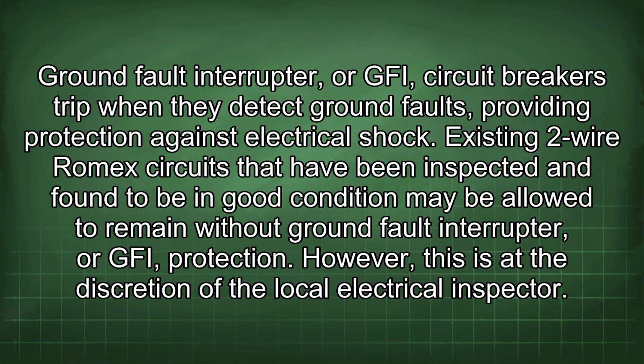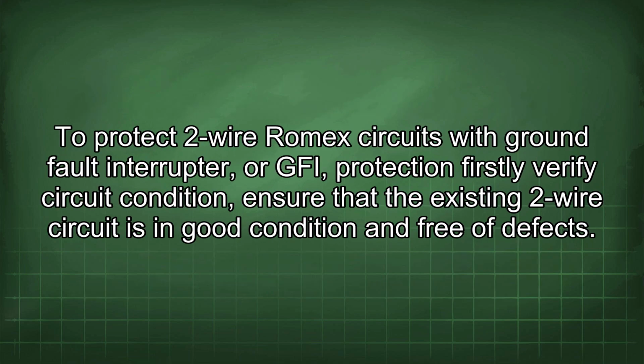Existing two-wire Romex circuits that have been inspected and found to be in good condition may be allowed to remain without GFI protection. However, this is at the discretion of the local electrical inspector. To protect two-wire Romex circuits with GFI protection, firstly verify circuit condition. Ensure that the existing two-wire circuit is in good condition and free of defects.